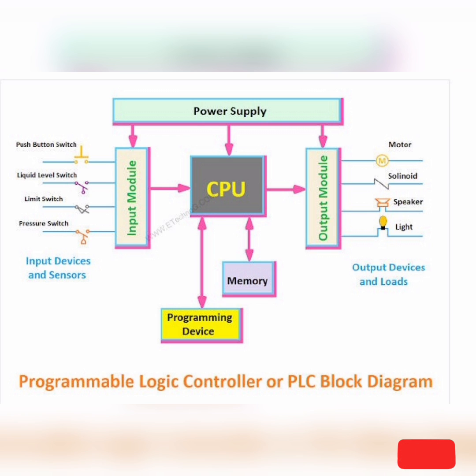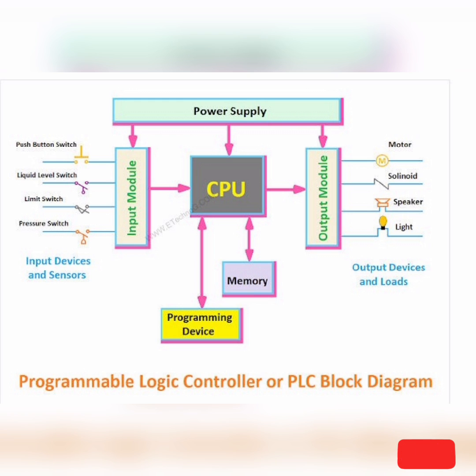Another important point is that the microprocessor can work with only digital signals, but all input devices or sensors may not produce a digital signal. In fact, most sensors create an analog signal. So another important function of the input module is to convert the analog signal into a digital signal. The microprocessor or CPU can deliver a very small amount of current — a few milliamps at 5 volts DC — so we cannot drive loads directly with the microprocessor. The output module solves this problem.